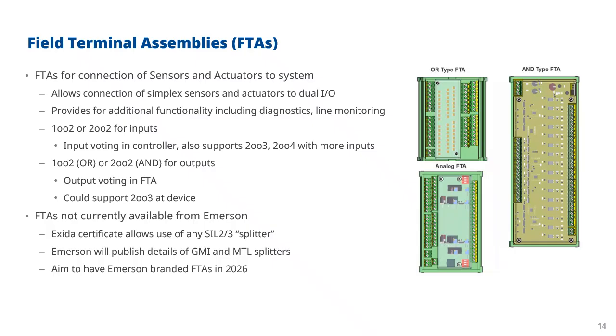Now, it was planned that Emerson would offer these field terminal assemblies. If you look at the Exida certificate, this says that any SIL 2 or SIL 3 splitter can be used. And at the moment, we're planning to publish details of splitters which are available from a company called GMI International and also from MTL. So they have a variety of different splitters available with different capabilities. And our aim is that by 2026, we will have Emerson branded field terminal assemblies, which will be in our price list and available from Emerson as well.